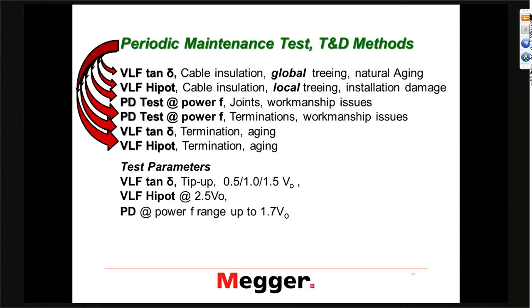VLF Tan Delta can also be an indication of aging in terminations. Especially when you look at the delta Tan Delta — where you look at the change of Tan Delta over different voltage steps — it can be a very good indicator of problems in terminations. Simply because you can have a lot of leakage on aged terminations, and that creates this effect. If we use a VLF hypot test on a termination, we have a choice between hypot testing and diagnostic test methods.